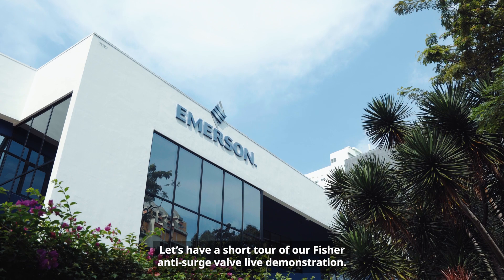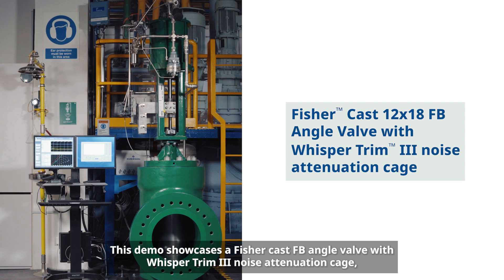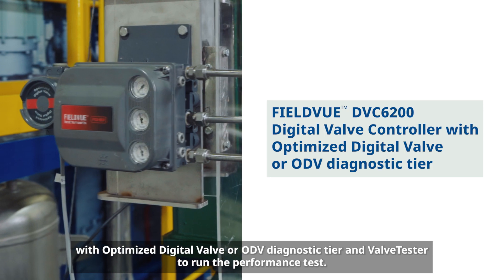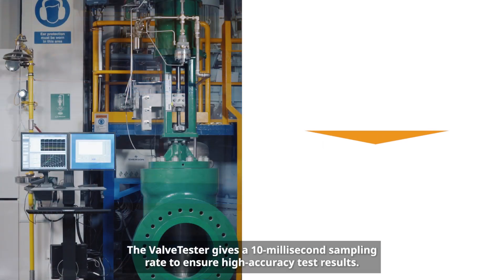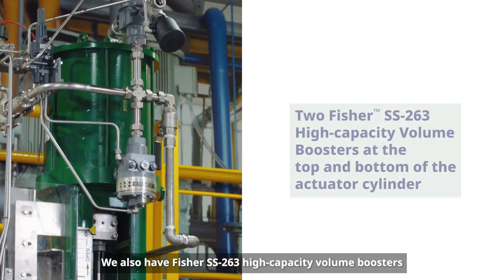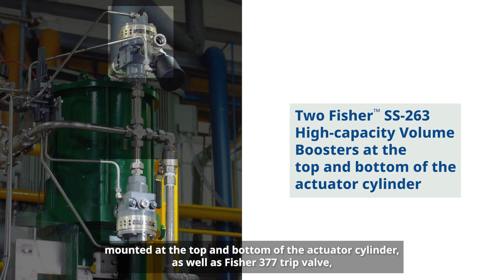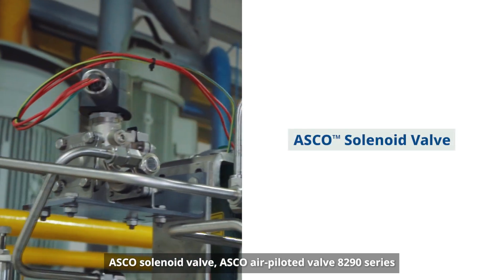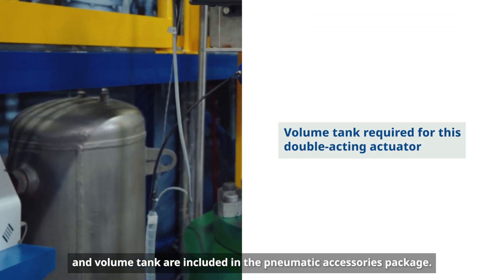Let's have a short tour of our Fisher anti-surge valve live demonstration. This demo showcases a Fisher cast FB angle valve with WhisperTrim 3 noise attenuation cage, Fisher 785C double-acting actuator, FIELDVUE DVC6200 with optimized digital valve (ODV) diagnostic tier, and a valve tester to run the performance test. The valve tester gives a 10-millisecond sampling rate to ensure high-accuracy test results. We also have Fisher SS263 high-capacity volume boosters mounted at the top and bottom of the actuator cylinder, as well as Fisher 377 trip valve, ASCO solenoid valve, ASCO air-piloted valve 8290 series, and volume tank included in the pneumatic accessories package.